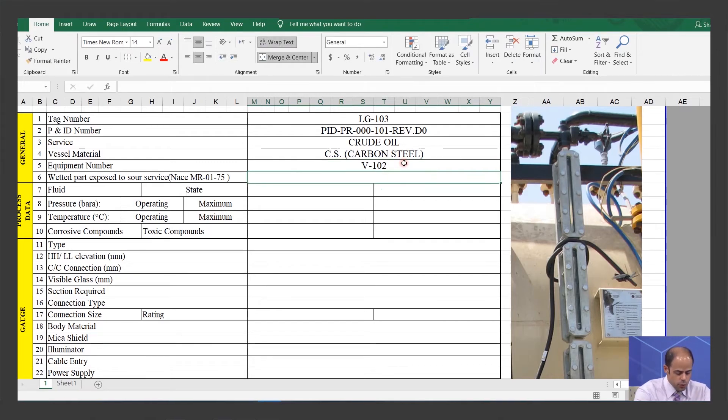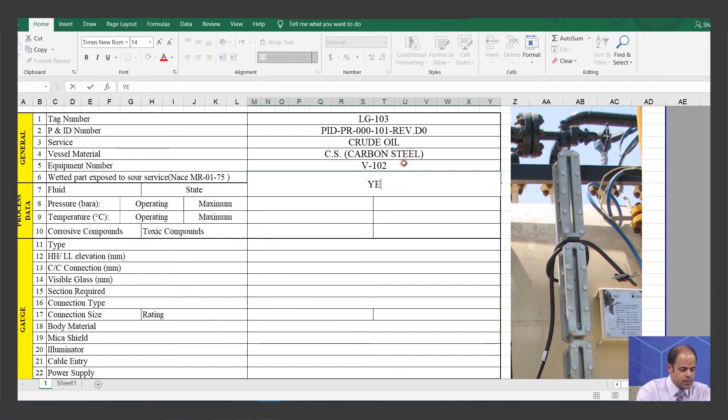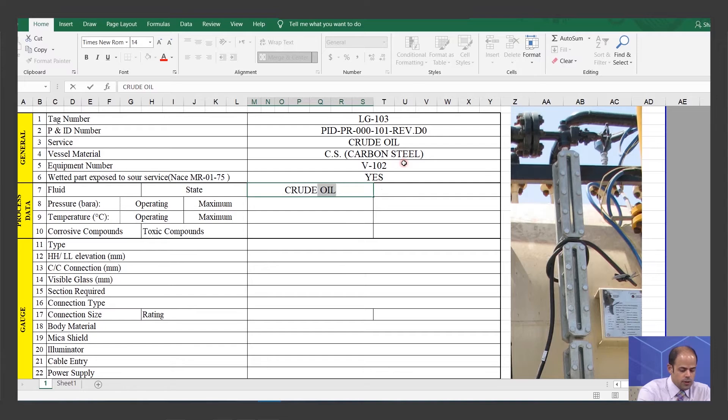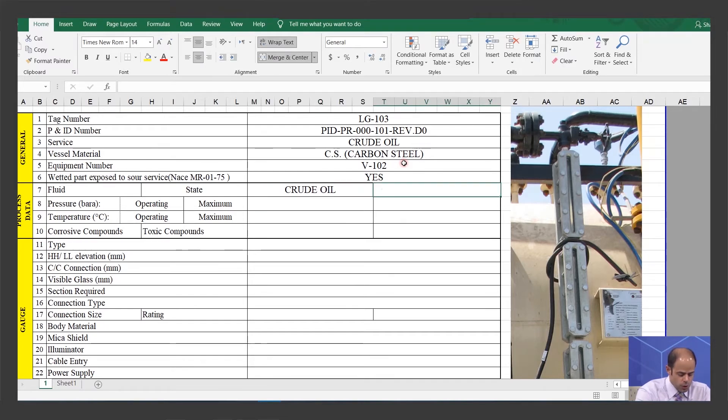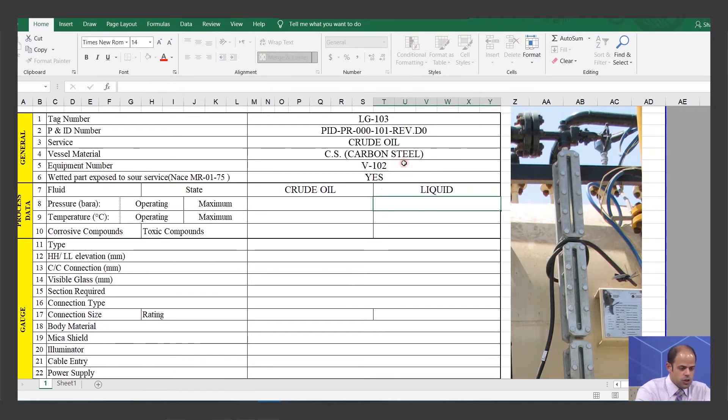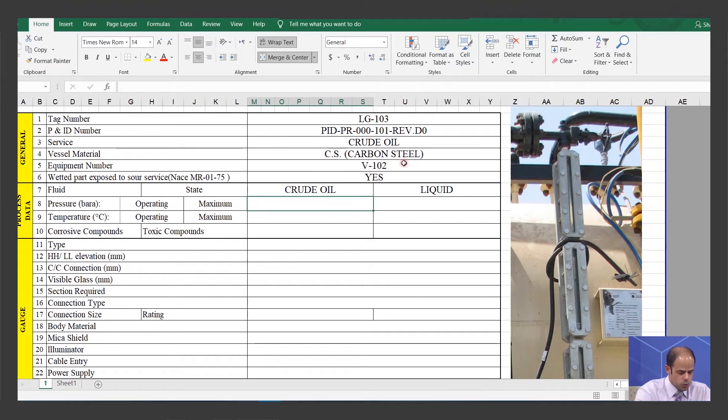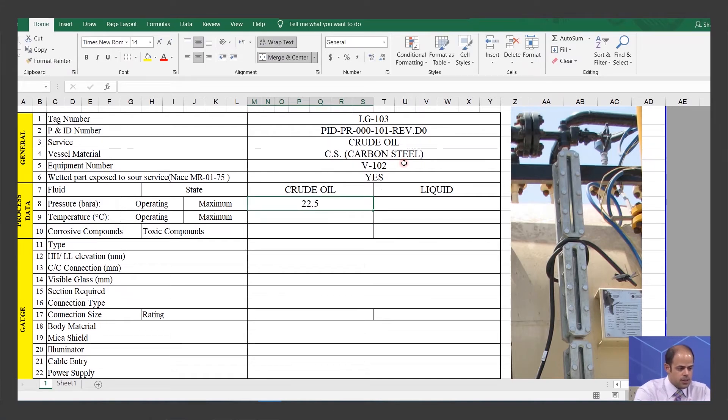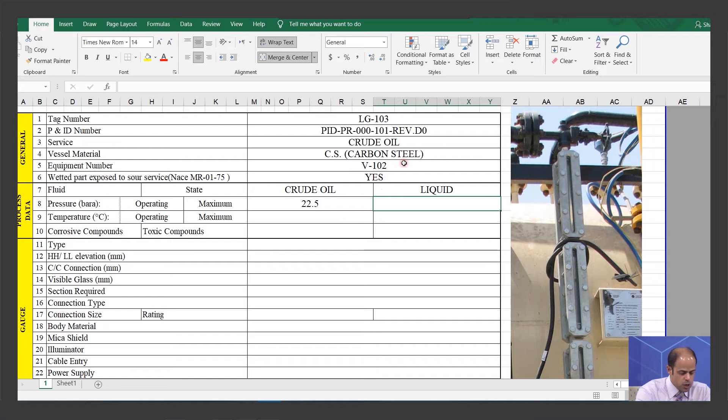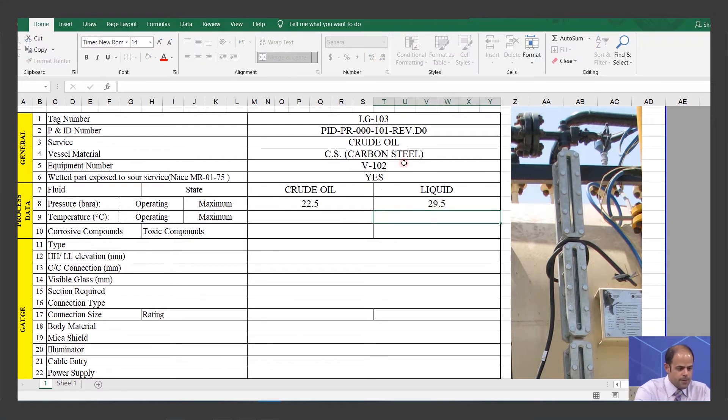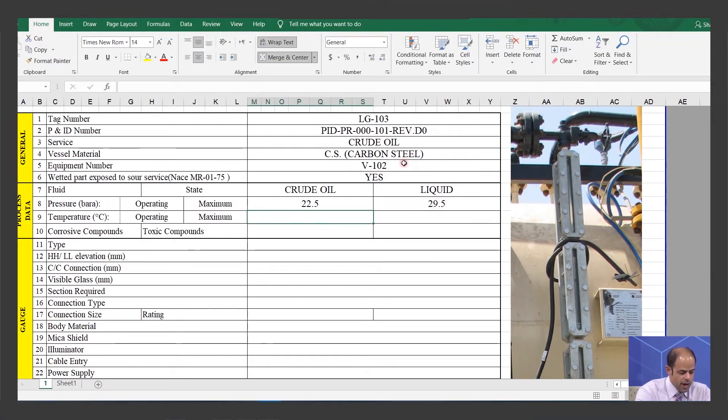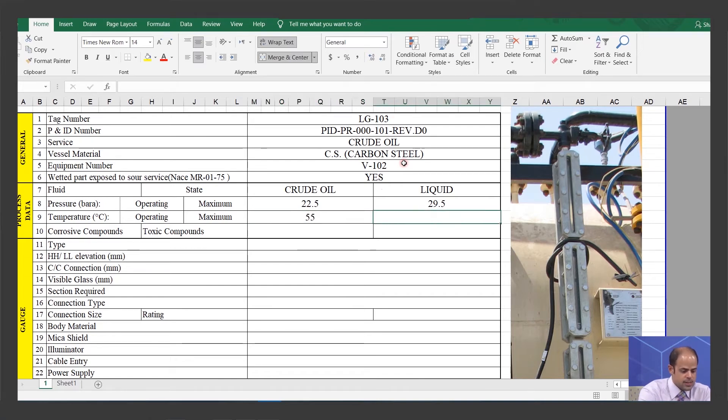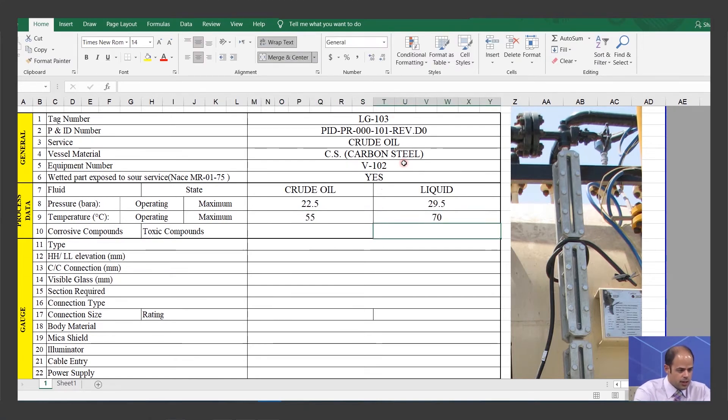Next, about the wetted part, the NACE standard is applicable for this part. This part is going to be filled up by process department. You can see it's crude oil and it's liquid. About the pressure, the operating is 22.5 bar absolute, and the maximum is 29.5. About the temperature, we have 55 for operating and for maximum or design, it's 70.